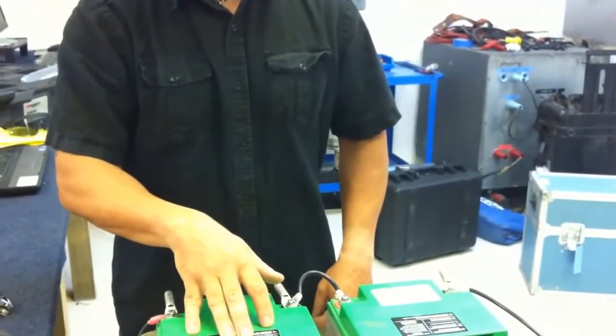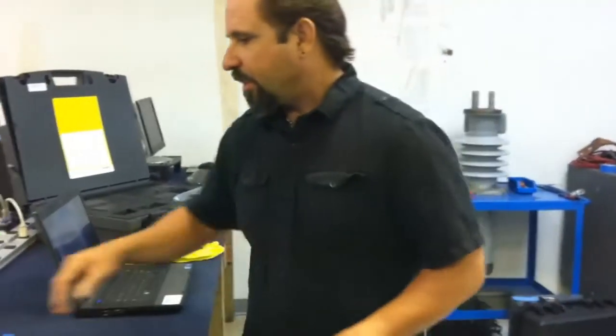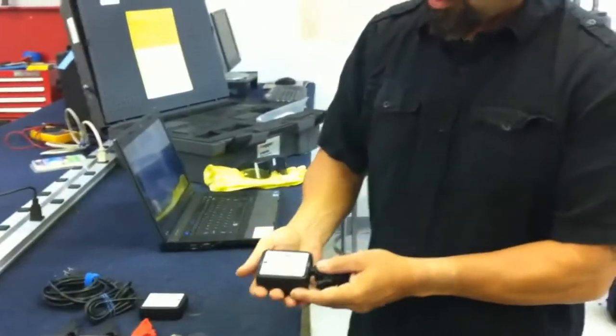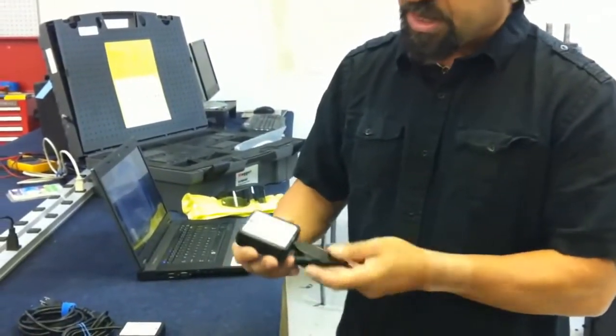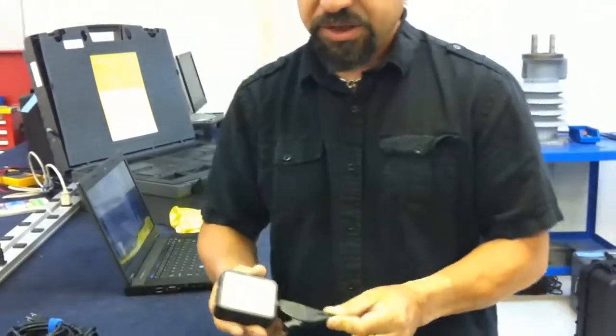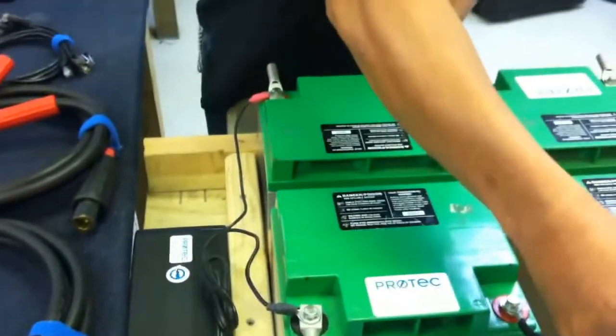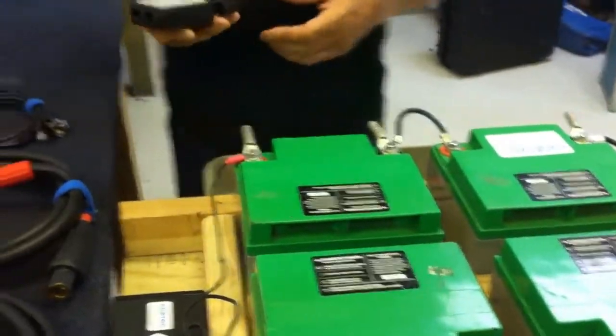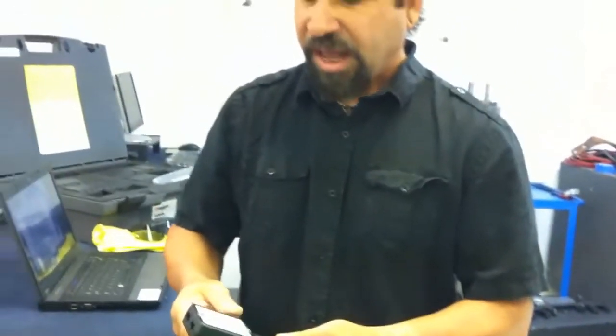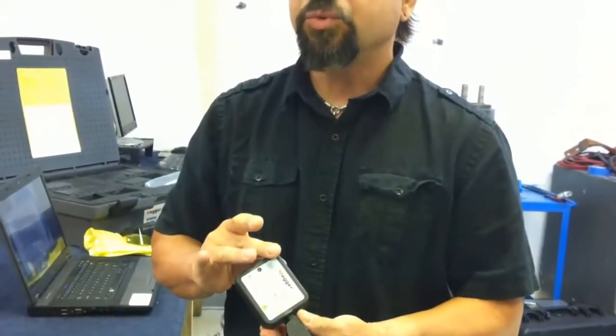Now, if you are following IEEE recommendations for load testing, you know that you also, during the load test, need to be able to monitor the individual voltages at each individual cell or each individual jar. For that, we offer the Megger BVMs, battery voltage monitors. These, in essence, are really just little voltmeters that will connect onto the negative terminal of each of the jars or cells in the battery bank, and will monitor the individual voltages at each of the battery jars.